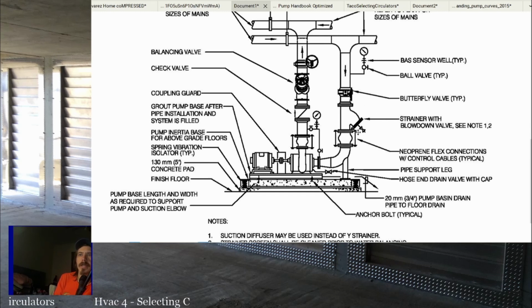You should have a flex connector, if at all possible, before the pump. That just helps isolate the pump from the piping system. You see a lot of pumps leaking at their flanges. Anybody ever notice that? Yeah. Pumps leak at the flanges a whole lot, don't they? Partially because a lot of times there are no flex connectors in there.